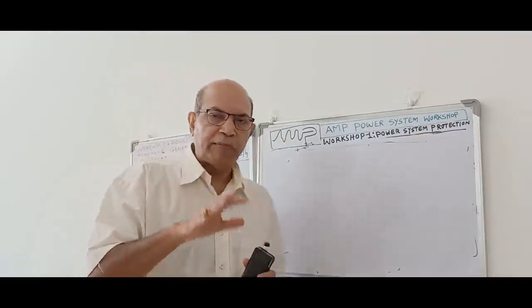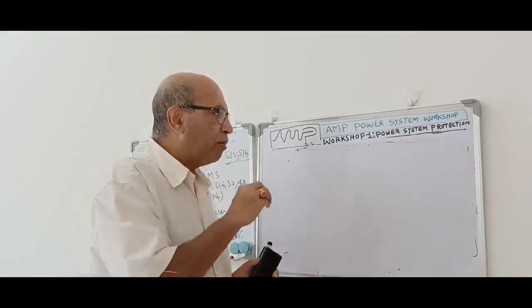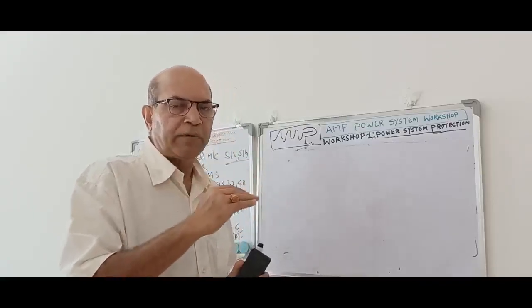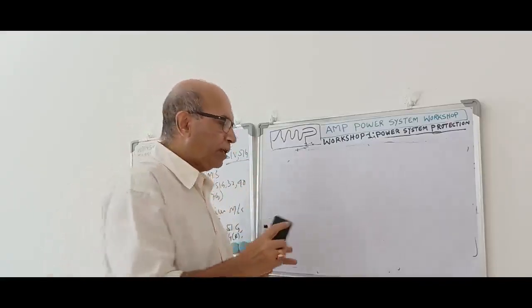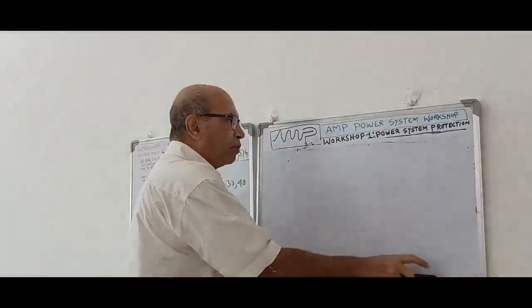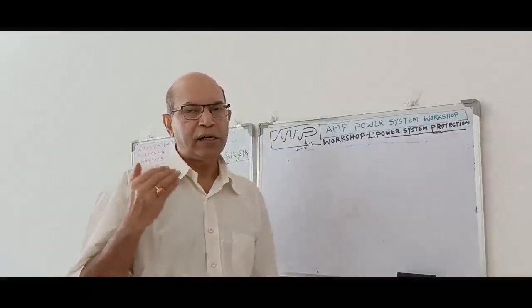So that we monitor by a low forward power relay, that is called 37. With the low forward power interlock, we can trip the generator breaker, field breaker, and the turbine, close the turbine fuel valve after some time. So these are the tripping schemes for the various types of generator. So with this, we are closing part 5 of session 6, generator protection.